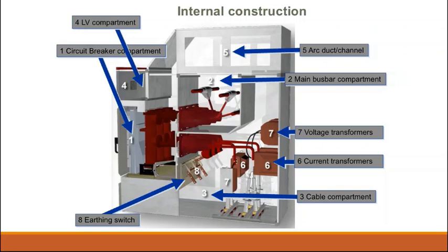And even here we kept a spare channel, a free channel, and here there is an LV compartment. The LV compartment will consist of the LV circuits. There are closing circuits, tripping circuits, even the status of the breaker, status of the isolator or earth switch, and the current circuit, voltage circuit, secondary, all wiring will be available in this LV compartment.